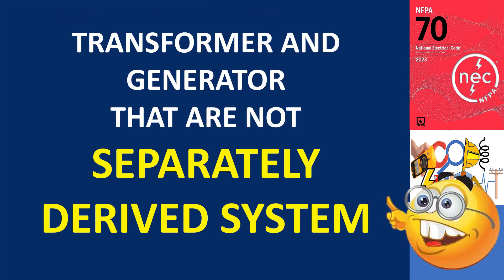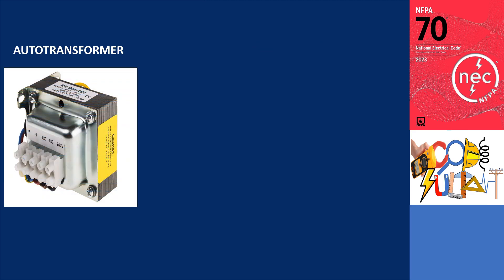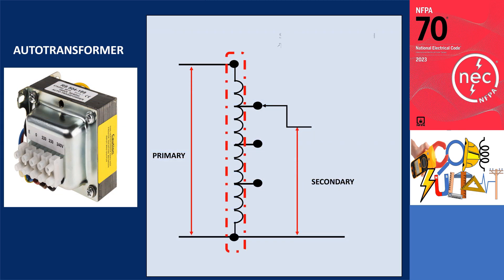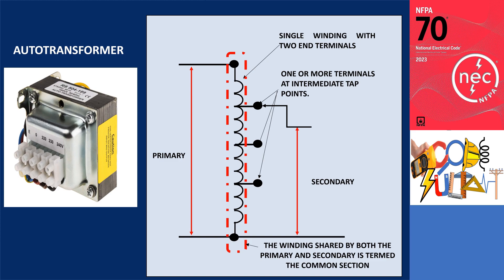It's worth noting that not all transformers and generators qualify as separately derived systems. An auto-transformer, for instance, features a single winding with two end terminals and one or more terminals at intermediate tap points. The segment of the winding shared by both the primary and secondary is termed the common section, thus establishing a direct connection to another source.